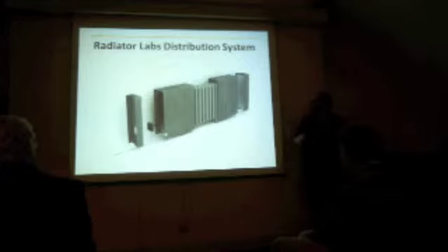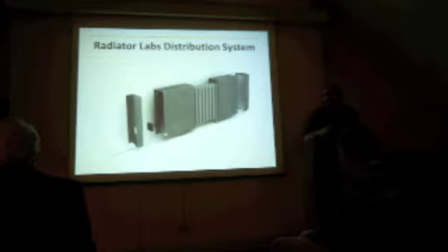There's a company called Radiator Labs. Essentially, they just put an insulating blanket over the top of it, a little computer fan, and a little duct blows air over the radiator and out into the room, and it insulates the radiator, so when you stop calling for heat, the radiator really does keep the heat inside of it a lot more than if you just let it radiate to the room. You avoid the hot spots and you get a much more even distribution.